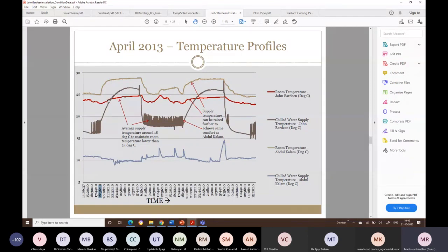If you have to deal with it actively, see, even in AHU, the way you would deal with it is by increasing the flow of the chilled water, right? Or increasing the delta. The same thing here. We are using the same chilled water. Okay? So the flow, the control, even in this, we use PICVs or control valves. Basically, if the temperature is achieved, the valve is cut off. Temperature is not achieved, the flow continues. So the control of flow of water controls how we take care of the load.